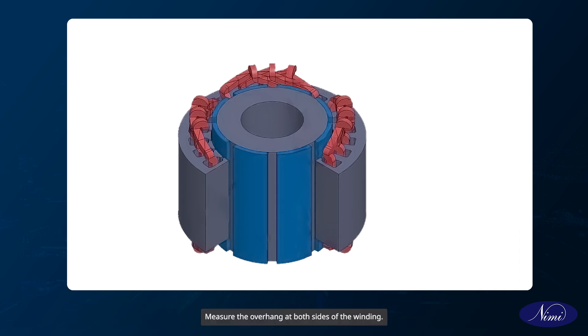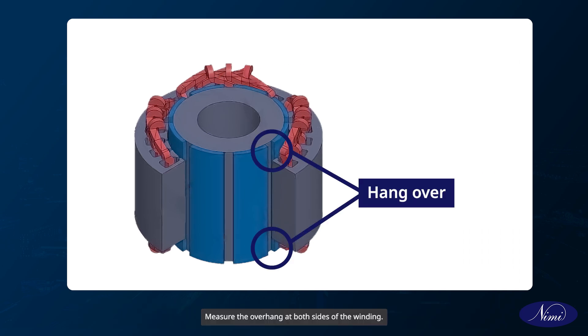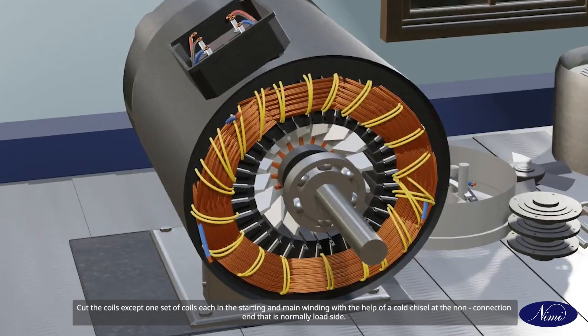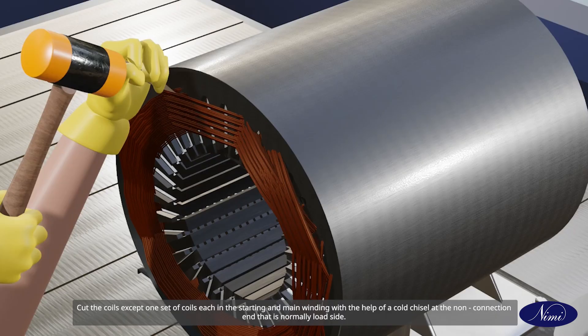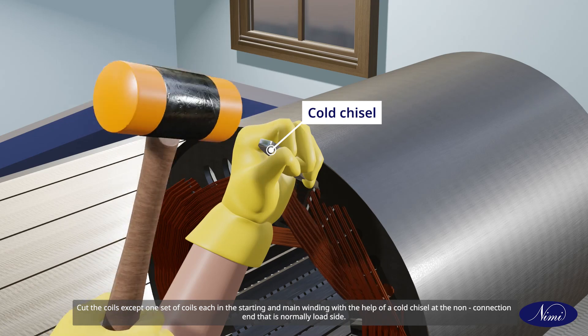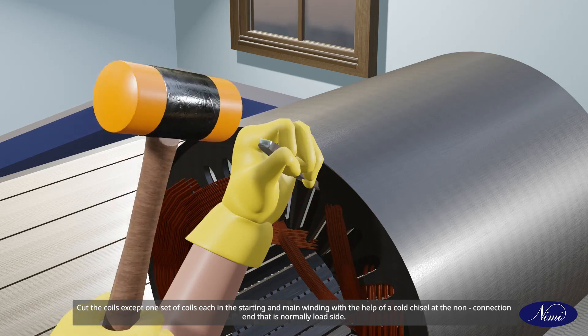Measure the overhang at both sides of the winding. Collect possible data like number of slots, coil pitch, etc. Cut the coils except one set of coils each in the starting and main winding with the help of a cold chisel at the non-connection end, that is normally load side.